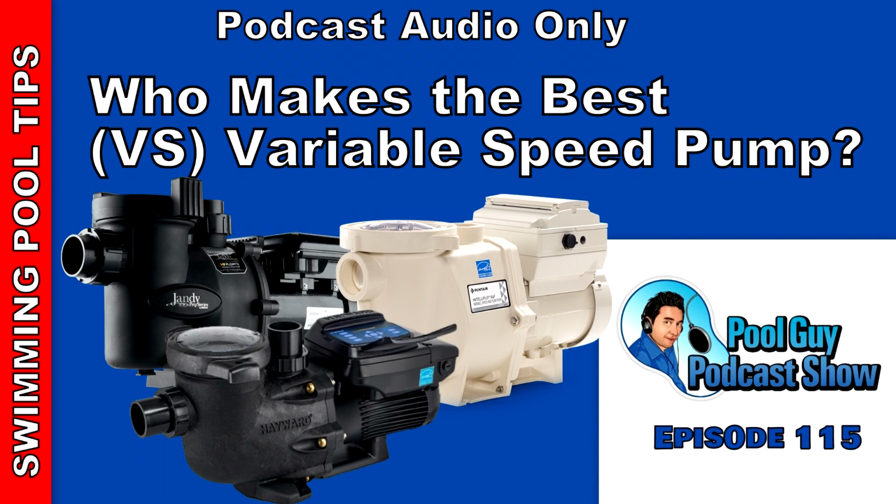And I guess I should note that the IntelliFlo uses the same footprint as the Pentair WhisperFlo, which is really popular in Southern California. So if you have a Pentair WhisperFlo, you can easily swap it out for a Pentair IntelliFlo with very minimal replumbing of the system, if any, depending on if you have unions connecting your WhisperFlo pump. So it's very easy installation. It'll be the same height, so if you have to cut the pipes, the IntelliFlo will fit right in there.